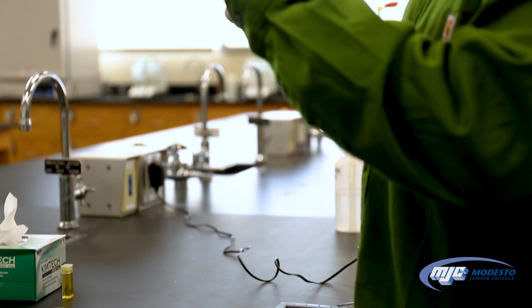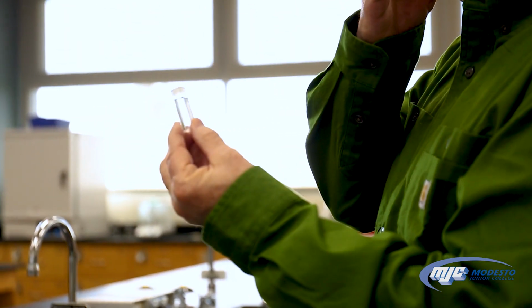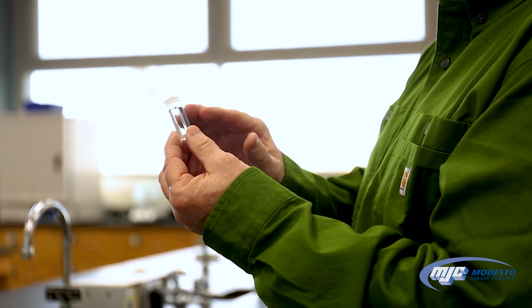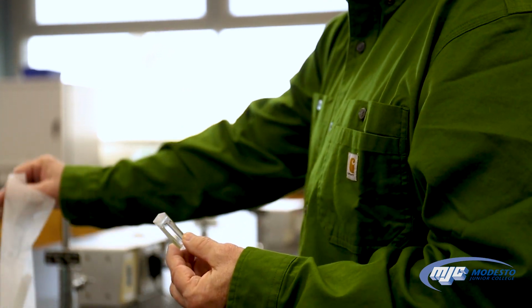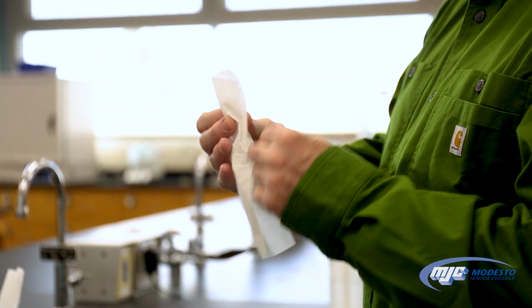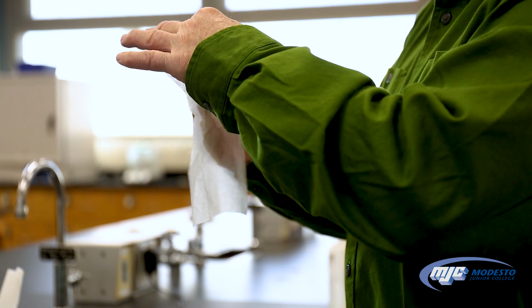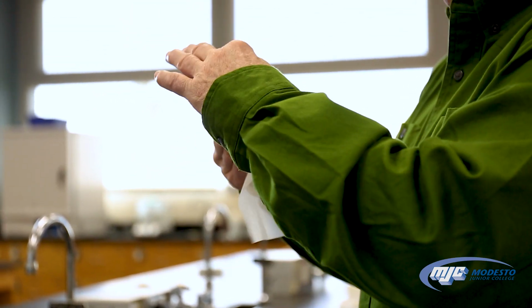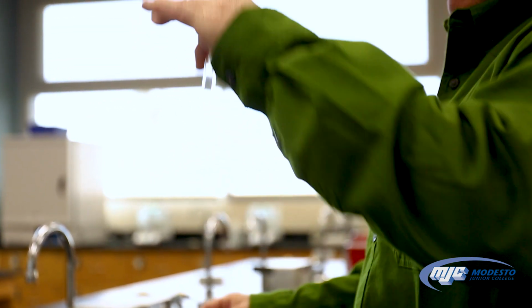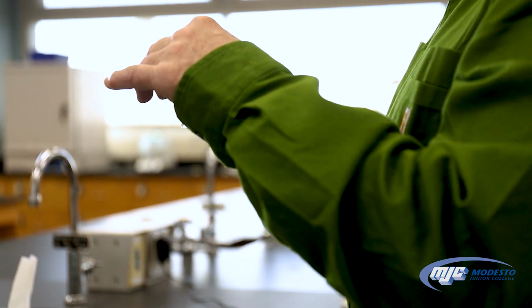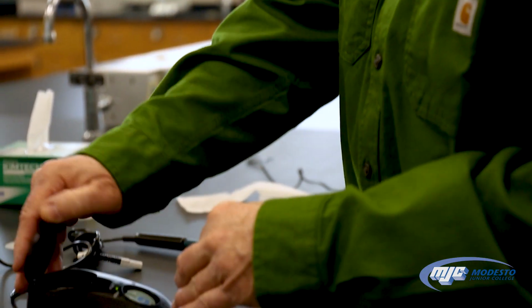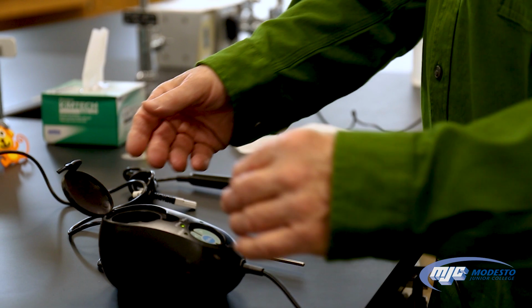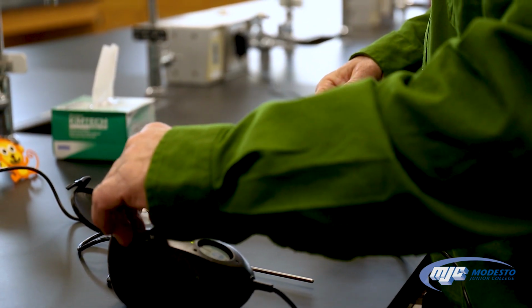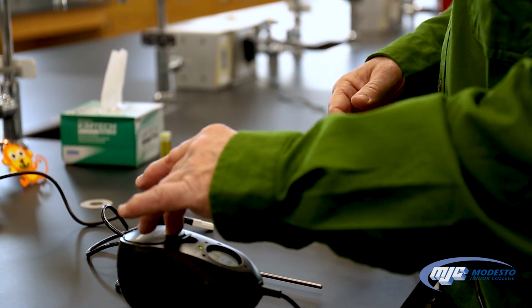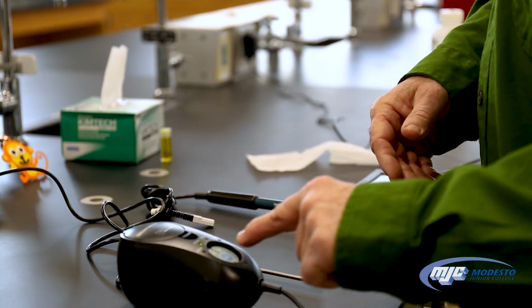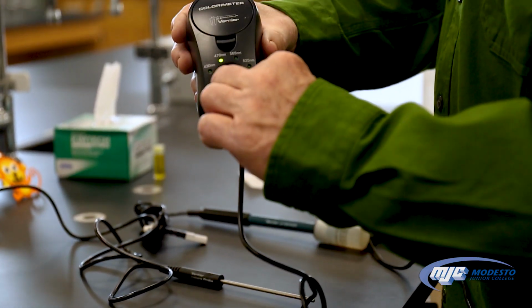To do that, you're going to need a cuvette, and in that cuvette there should be, most of the time, just deionized water. Take a Kim wipe and always clean off the outside of the cuvette right before you put it into the colorimeter. Make sure there's no marks, no air bubbles either. If there's air bubbles, you need to get them out. Pop it right into there. Close the lid. And press the cal button, this button right here.